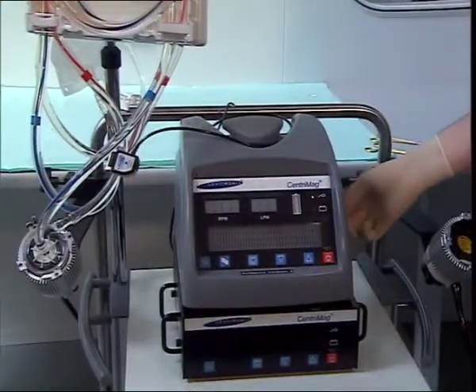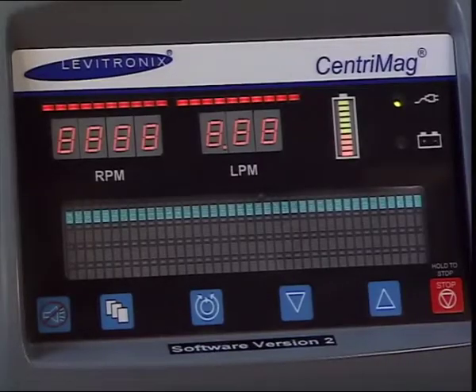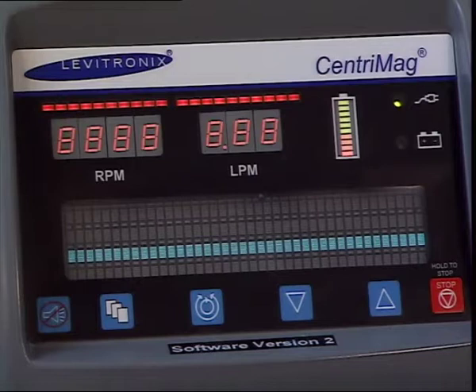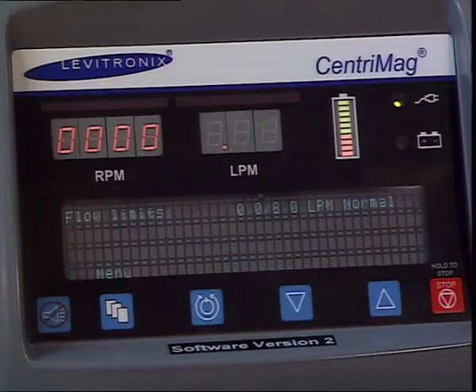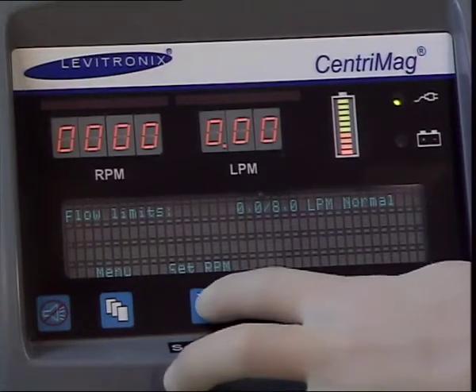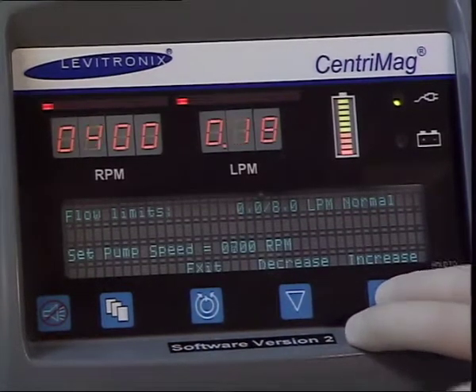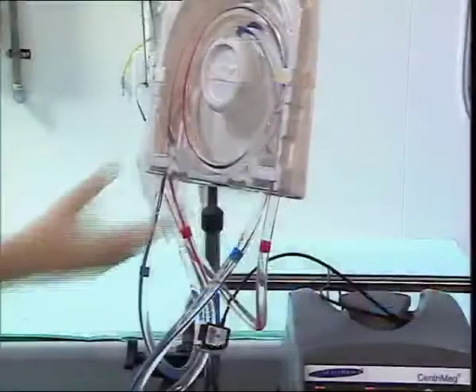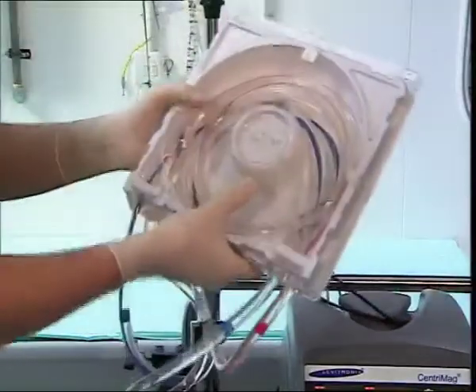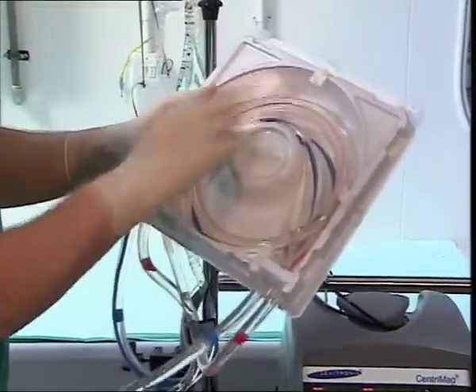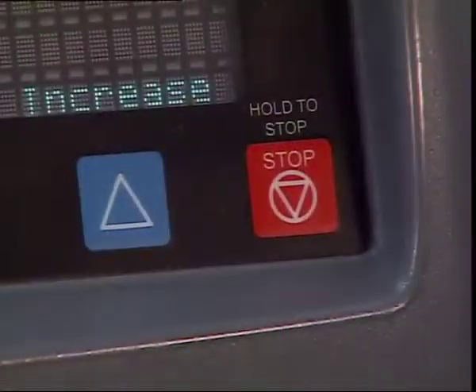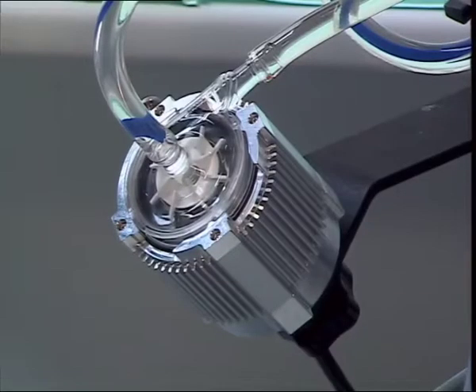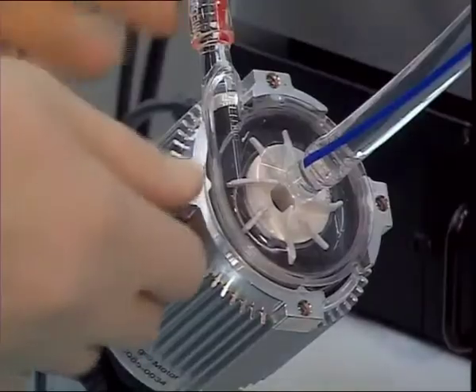Turn the system on and allow it to self-test. Generate forward flow by pressing the Set RPM button, followed by the up arrow. Once forward flow is established, remaining air should be removed. It is important to check the pump head for air, so stop the pump, remove the head and agitate it gently.